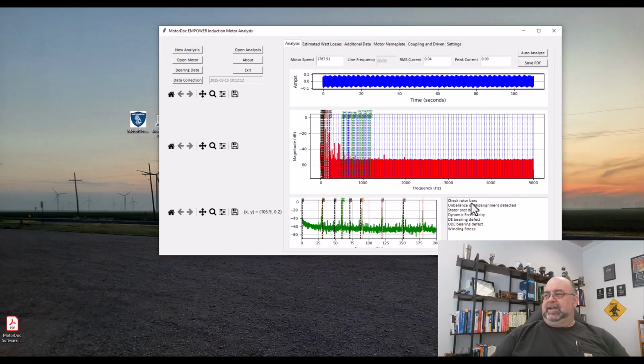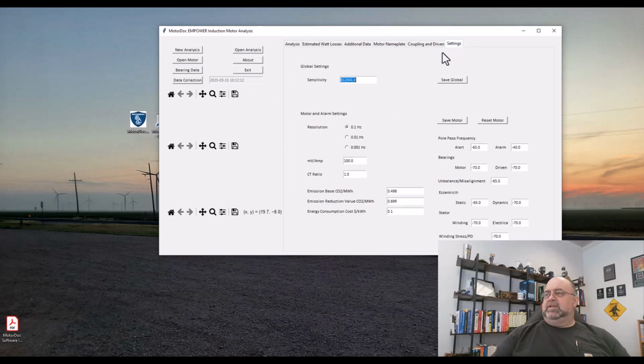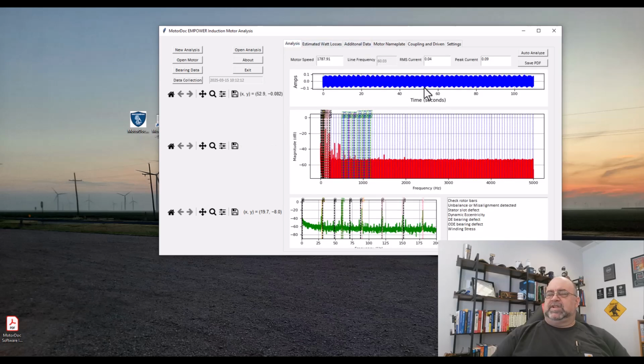So now apparently in addition to what I actually have, I now have a stator slot defect and a dynamic eccentricity. So now I have 1, 2, 3, 4, 5 false positives off of ground, but this signature looks a lot closer, and it's also close to the original speed. So I'm getting better data off of this. Very high raised noise floor. The alarm settings are where they need to be, so they're not overly sensitive.